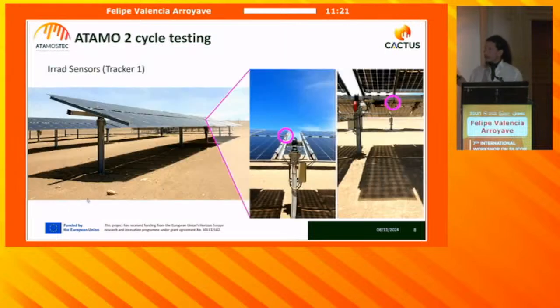So, in this solar platform, we have about 300 sensors. All of them are fully integrated in a homemade monitoring system that we use to operate these platforms remotely, because putting people there is quite difficult, and going there so often is also a very time-consuming, money-consuming and finally resource-consuming task. So we have different reference cells in the front, in the back.